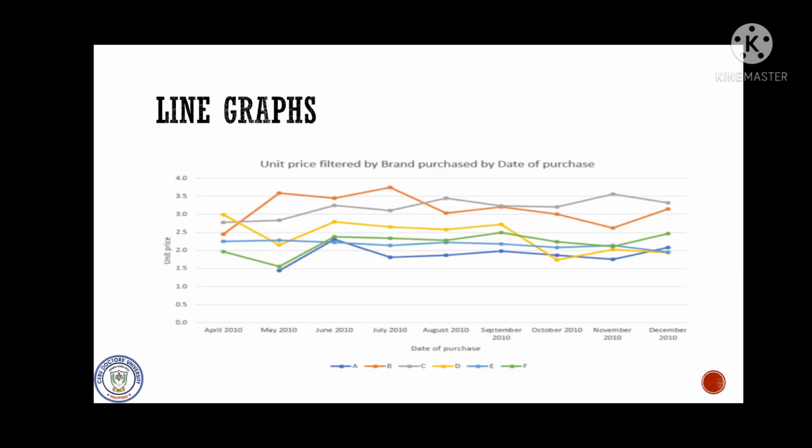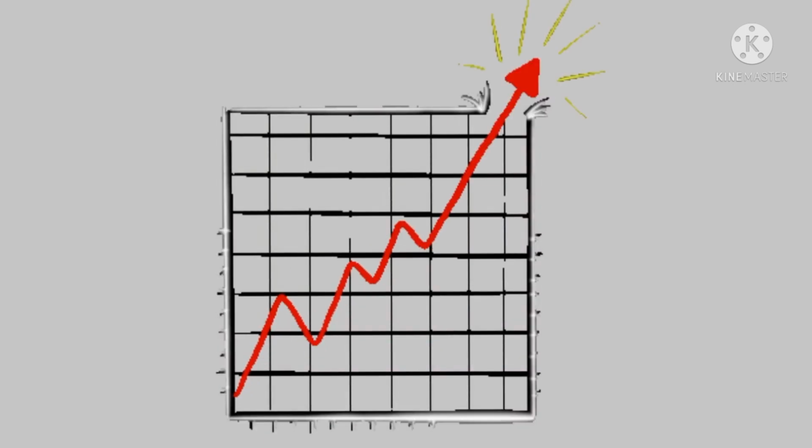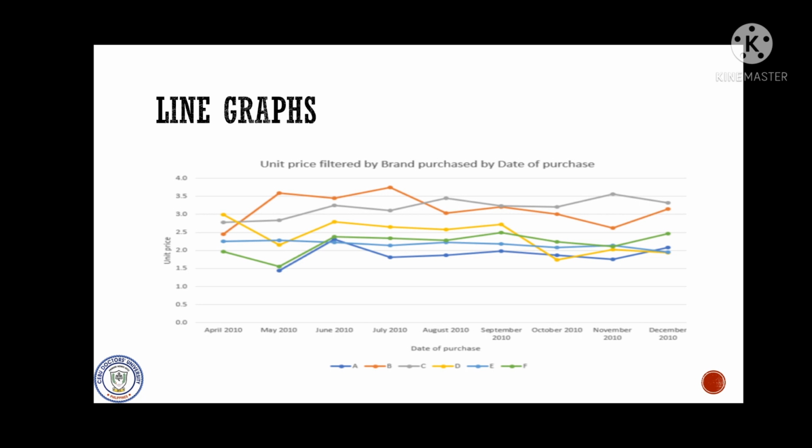And lastly, under basic statistical graphs are line graphs. These are particularly useful for plotting and tracking data over a period of time. So if you connect the dots on a Levey-Jennings chart, for example, you have a line graph automatically. Line graphs are very adaptable for displaying historical data. Control values, instrument parameters, workload volume, and blood bank refrigerator temperature monitoring are only a few of the many uses of the line graphs in the laboratory. When these values are plotted over a period of time, the patterns may be quite revealing about areas that need attention and require improvement, especially trends or deterioration in reagent or instrument performance.